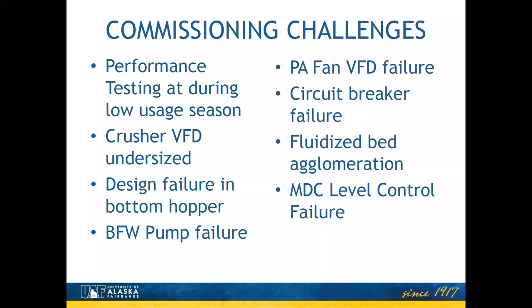Once we got past that one, then we started running the boiler at increasingly higher rates, and we had another electrical failure in the transformer that runs the variable frequency drive that turns the 650 horsepower primary air fan. And that primary air fan is the thing that fluidizes the bed. So without it, the boiler just doesn't run. And it had an unusual failure in it that Mike just went back to the manufacturer's facility in New Jersey a week ago, along with a forensic engineer who examines transformer failures, and we're awaiting the final reports from everyone, but it's pointing towards a manufacturing flaw in it. So with some help from the manufacturer and a lot of scrambling on university staff's part and our staff's, we were able to find a replacement VFD and get it back into service within a couple of weeks and got past that one.